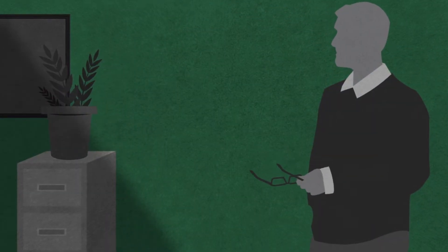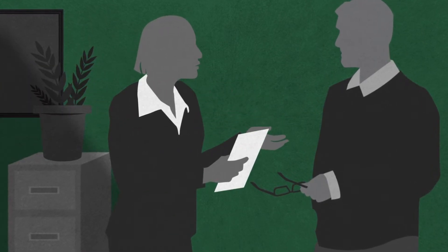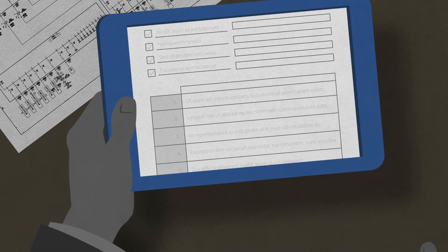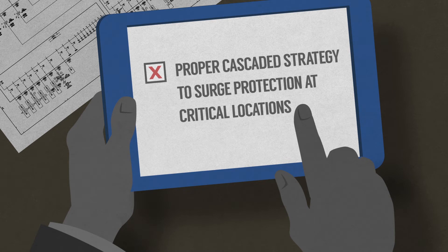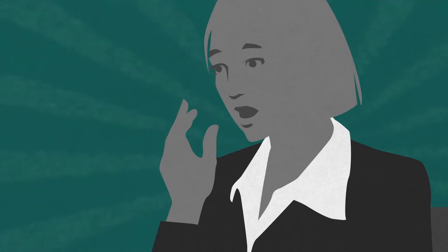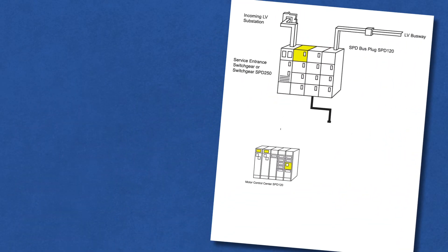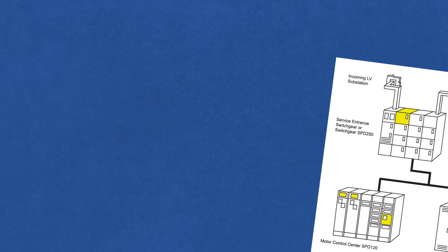At 11 a.m., Allison has an appointment with her Eaton rep, Tom. Allison asks Tom if he has any ideas on this perplexing problem. Tom has just completed a thorough review of the hospital's electrical system. He points out to Allison that the hospital is not using the proper cascaded strategy for surge protection at critical locations, which can actually lead to early failure on modern LED bulbs. Allison is surprised when Tom tells her that most of the damage may be coming from power surges originating within the hospital.